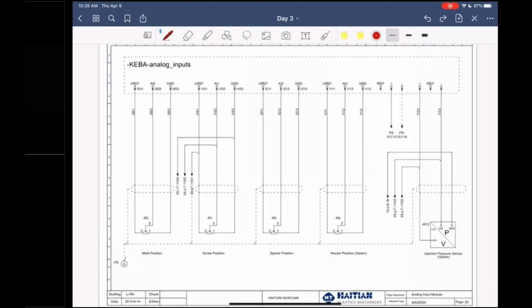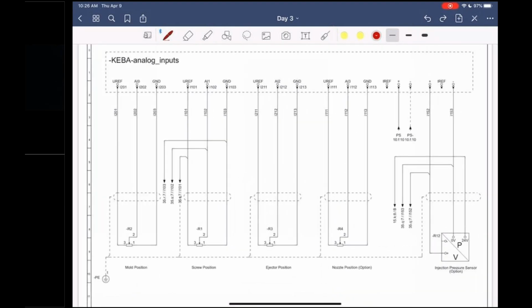Analog input module. Again, this is where all your positions are, your Temposonic rods. So you have a U reference, you have an analog input 0, and then you have your ground. If anybody's curious how these work, it's just a variable resistor. The voltage range is 0 to 10 volts. As the transducer moves back and forth, it varies the resistance. When you vary the resistance and put a voltage to it, the voltage changes coming out of the other end. So when it reads the voltage, it's actually reading a different voltage between 0 and 10.